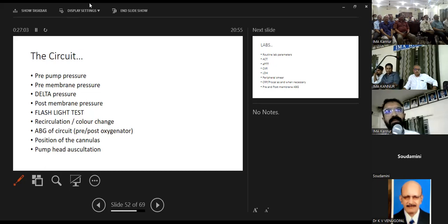For each company, it's a different delta pressure. Then the flashlight test, which should be done daily. It's a simple test where you shine a torch on the oxygenator to look for any clots. Okay. Recirculation, the color change of both the tubes, you should check.